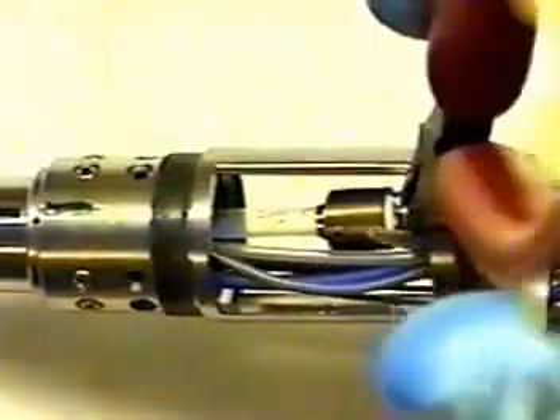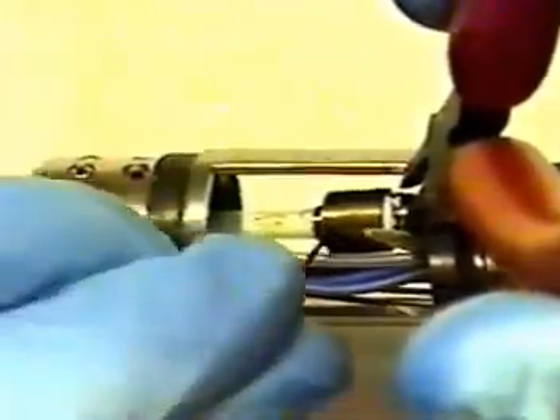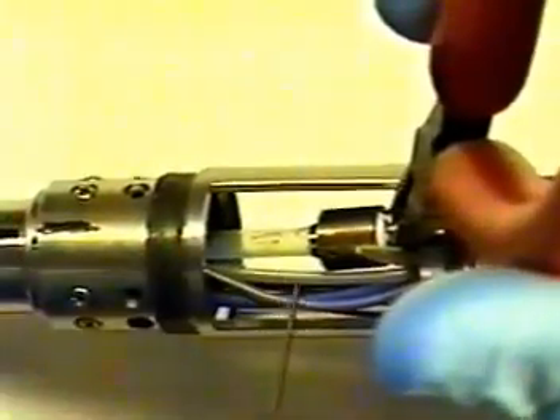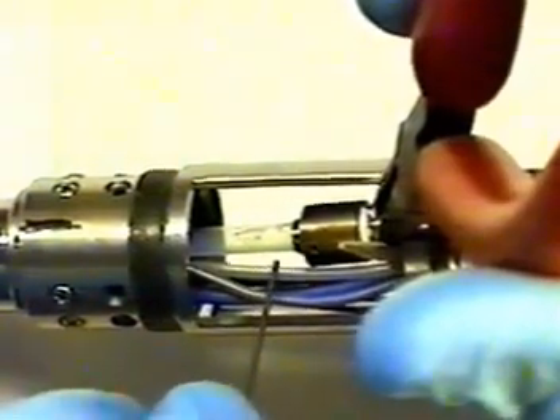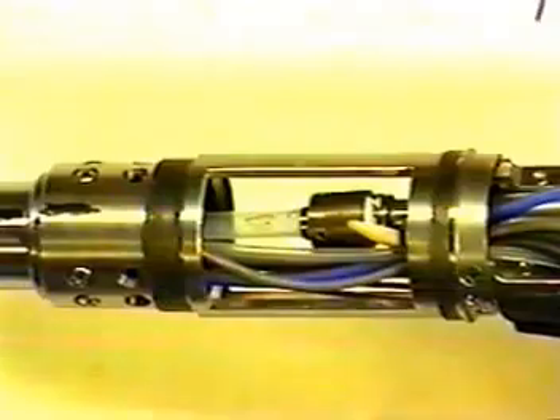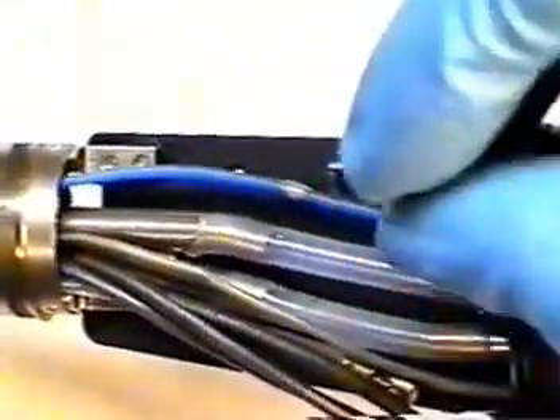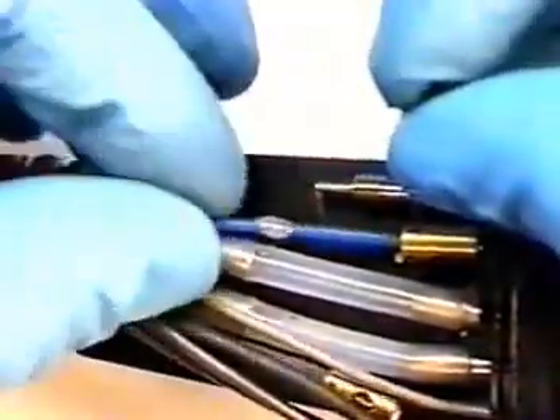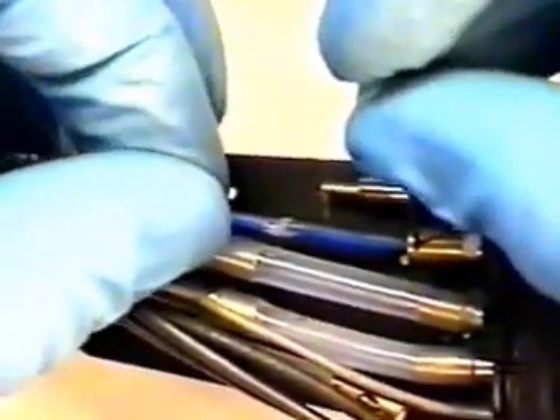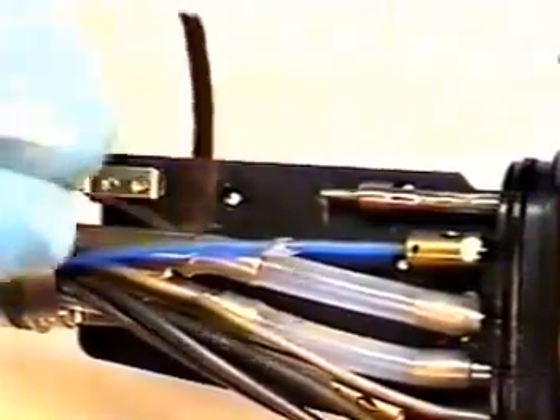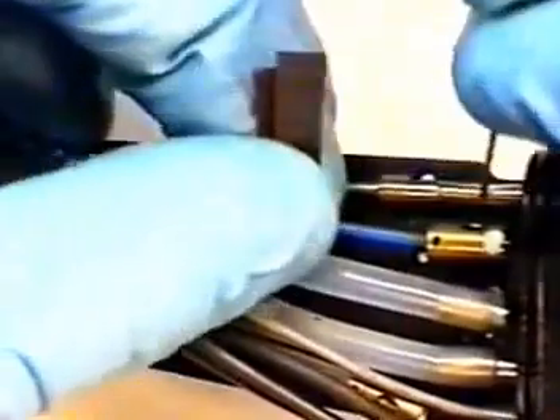It may be necessary to hold forcep port assembly while finally tightening your ferrule up onto forcep port. Be extremely careful not to kink or cut into any of the channels or illumination bundle. Reattach air and water channels using the same principle, not to let channel twist while tightening each ferrule. If you find the channel is twisting, you can use a small piece of cut emery cloth to put underneath and hold channel while turning ferrule. This will restrict the channel from twisting inside body insertion tube.